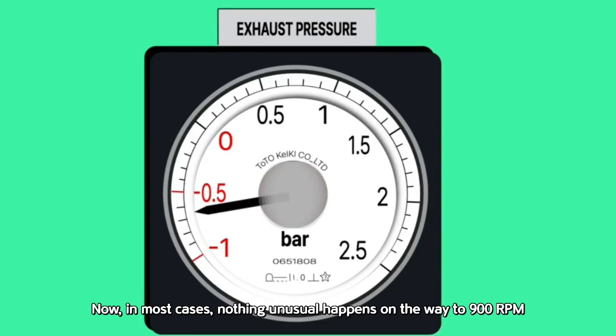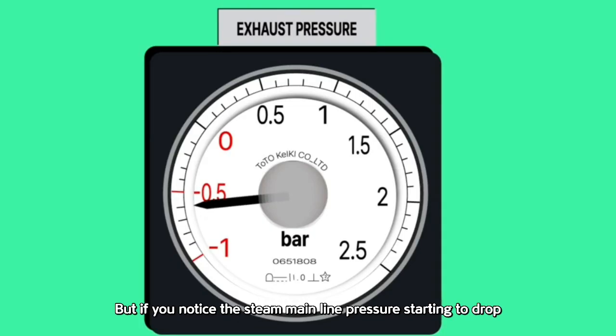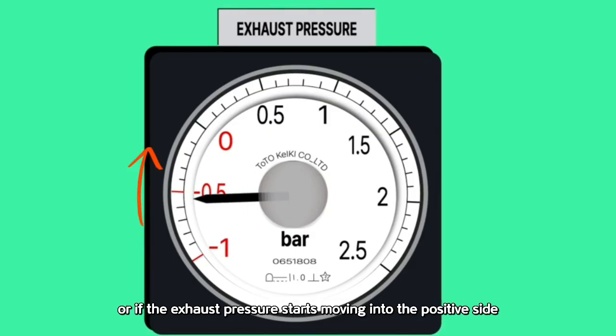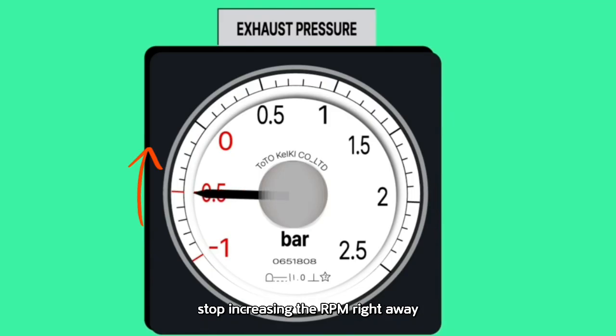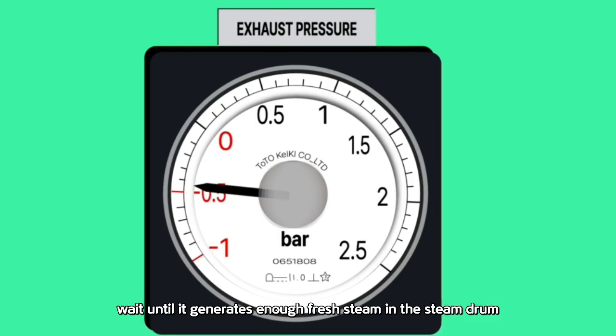Now, in most cases, nothing unusual happens on the way to 900 RPM, but if you notice the steam mainline pressure starting to drop, or if the exhaust pressure starts moving into the positive side, stop increasing the RPM right away. Give the boiler a moment to catch up. Wait until it generates enough fresh steam in the steam drum before you continue increasing the RPM.